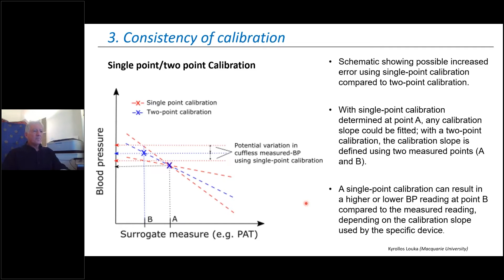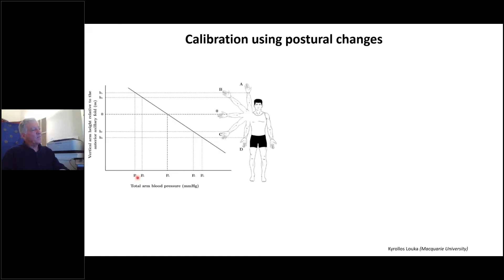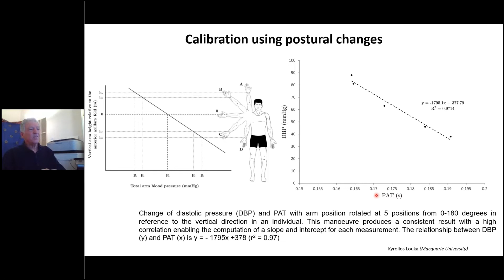The second point is, how do we obtain reliable or reproducible changes of blood pressure that we can calibrate the instrument? So if one measures pressure in the arm at different locations, 45 degrees, you can obtain, in fact, quite a good reproducible estimate of blood pressure with arm position. And so if one were to do that, you could obtain a calibration curve. And so this calibration curve with blood pressure and pulse arrival time at different points, right, could be used then as a metric.